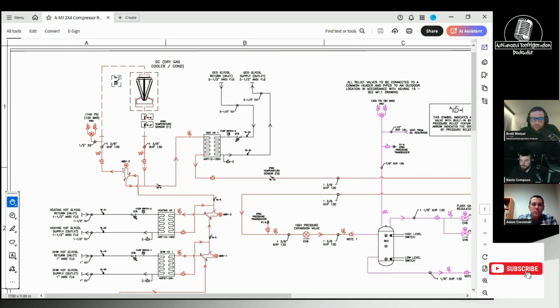So when you set these systems up, look at the sequences and make sure that the set points between one control point and another are far enough apart that you're not competing and struggling. Give each their own little space. For example, the gas cooler set point is 60, the fan shuts off at 55, the high pressure valve regulates at 50, and then maybe the bypass is at 45. So you've got a 5-degree dead band in between to prevent competition on the control loops, if that makes sense.